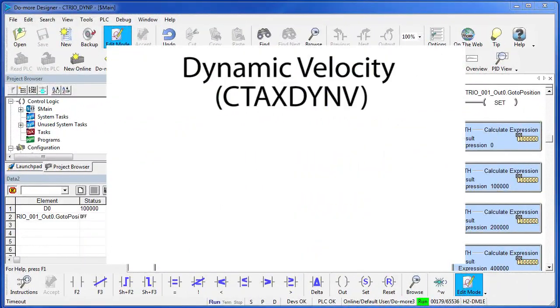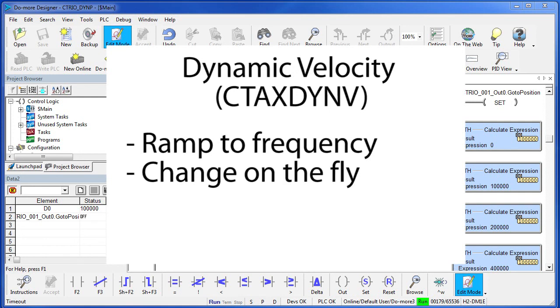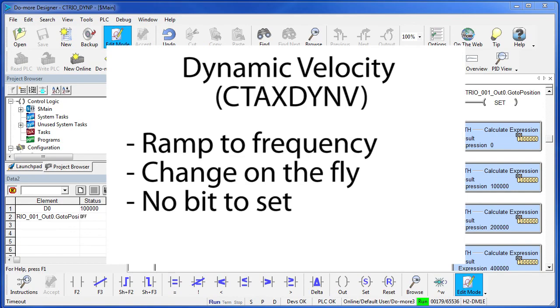The dynamic velocity command allows you to ramp to a specified frequency and it allows you to change that frequency at any time dynamically. The good news is you don't need to toggle a bit with this one though. All you have to do is change the frequency and it will follow.